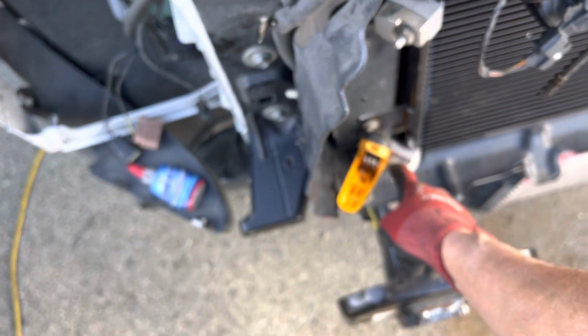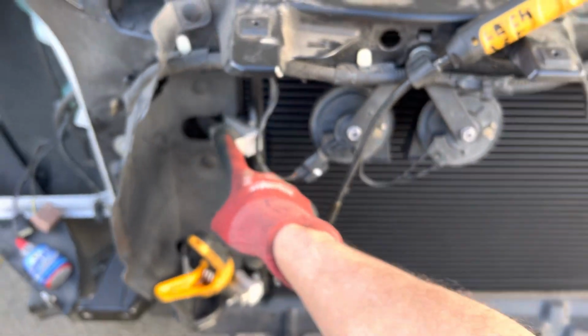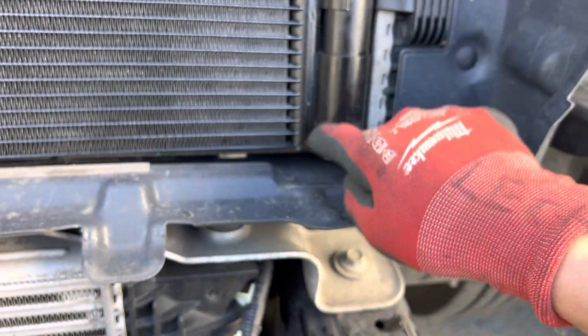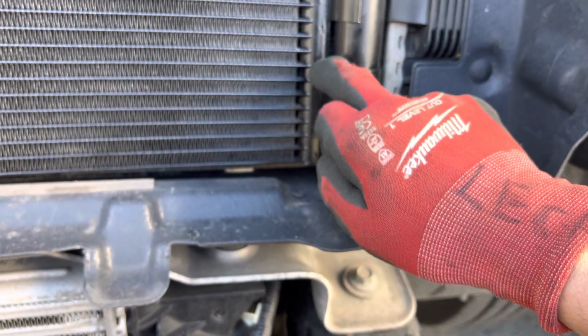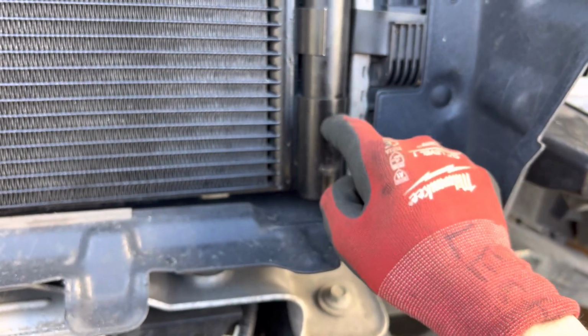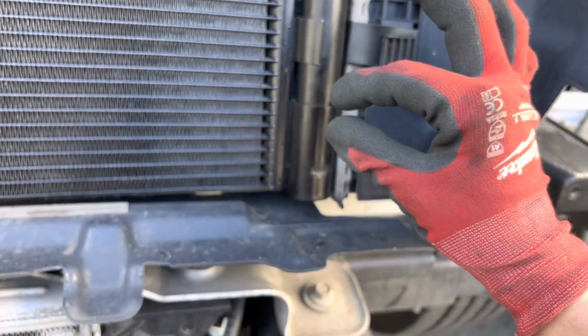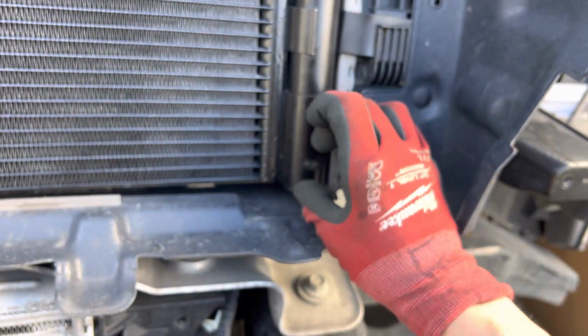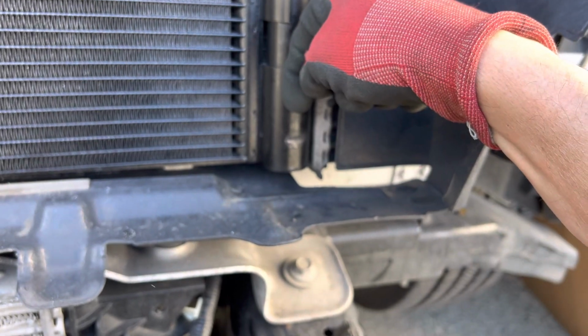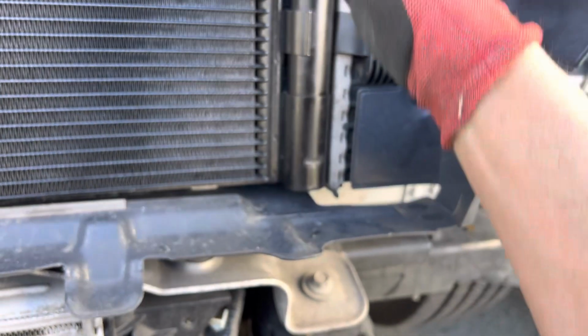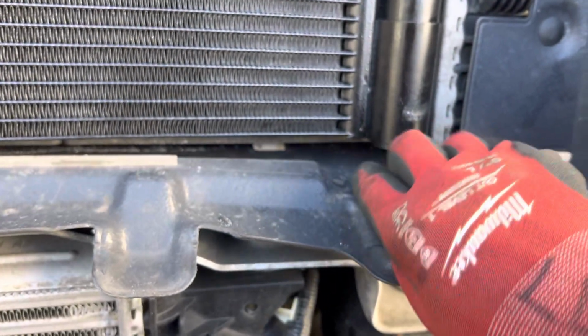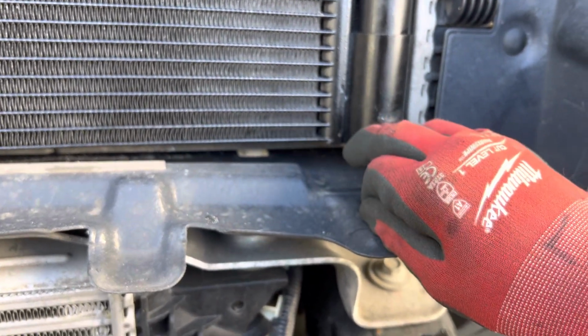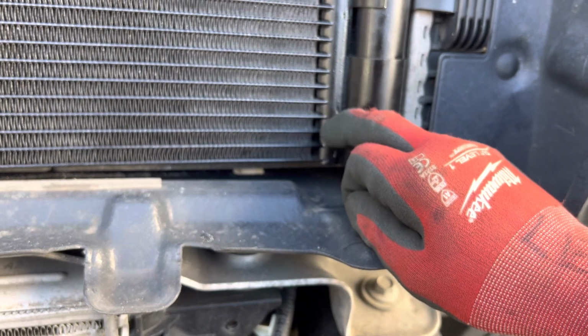Okay, now let's look how the subcooling changes. So here's the temperature of the refrigerant. It goes in as a hot vapor right here. Then it's making its multi-passes. Then it's going into, there's a little port somewhere right in here. Somewhere right in this little area, there's a port that is drilled to go to this receiver dryer that has the desiccant material, so it can separate out the refrigerant oil as a liquid down, and it goes through a screen right here and it drops down through a port. I've done videos on this where I've cut these open in half and I cut that line to show you how the ports change. And then right here, I think it's right between these dimples. So nope, that's not a seal. 1, 2, 3, 4. I think it's somewhere 3 or 4.